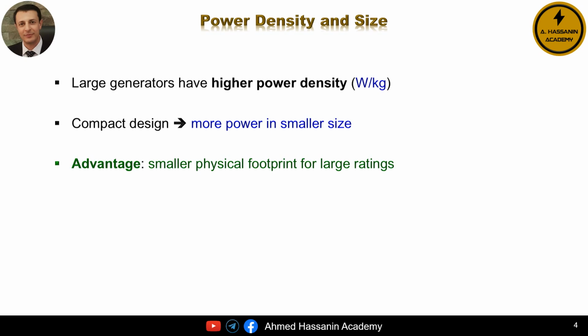What does that mean in practical terms? It means that large generators are designed to deliver more power without becoming proportionally heavier or bulkier. In other words, you get more output from a relatively compact machine. This is a big advantage in power stations. A higher power density allows engineers to install very high capacity generators without occupying excessive space, which reduces construction costs and simplifies the overall layout of the plant.